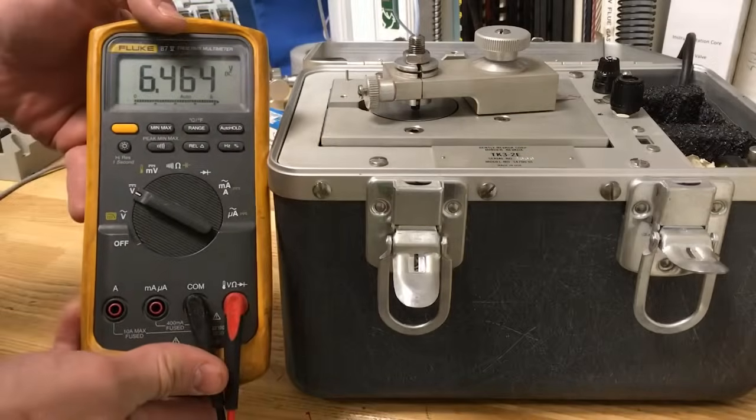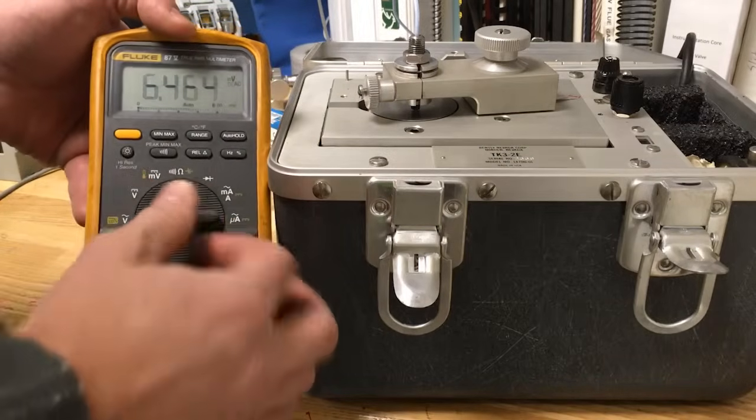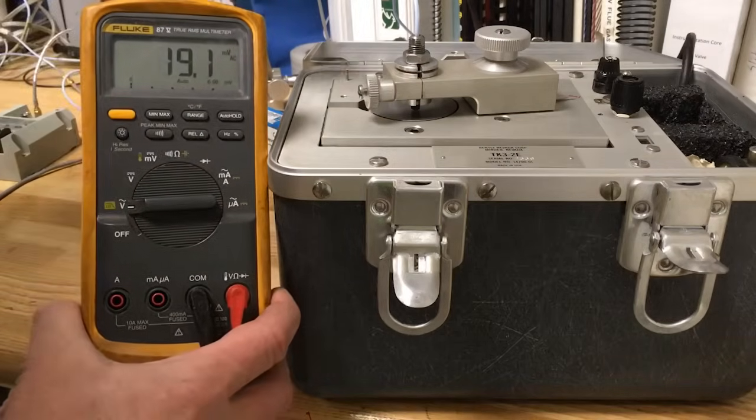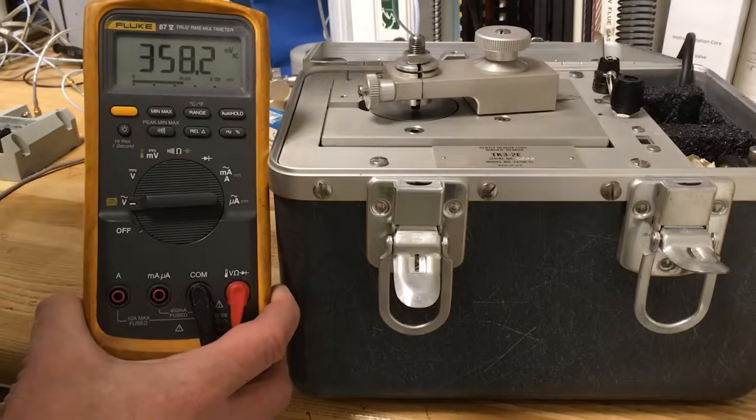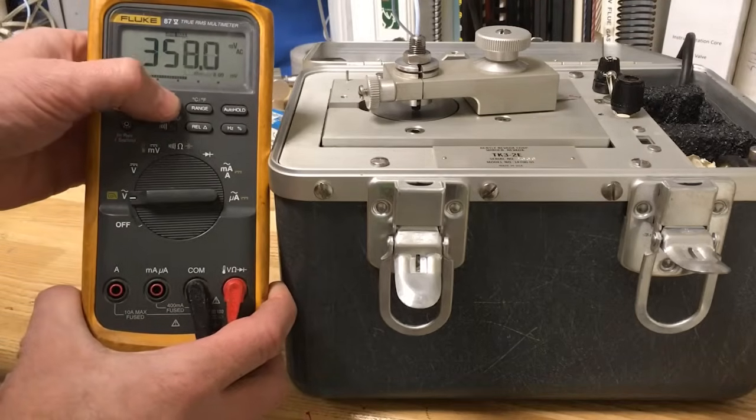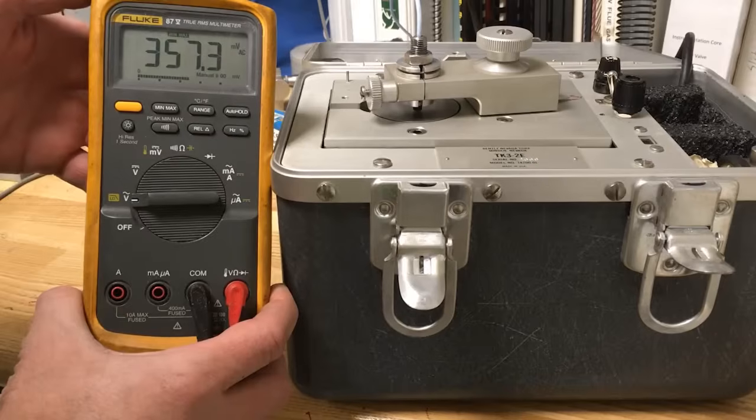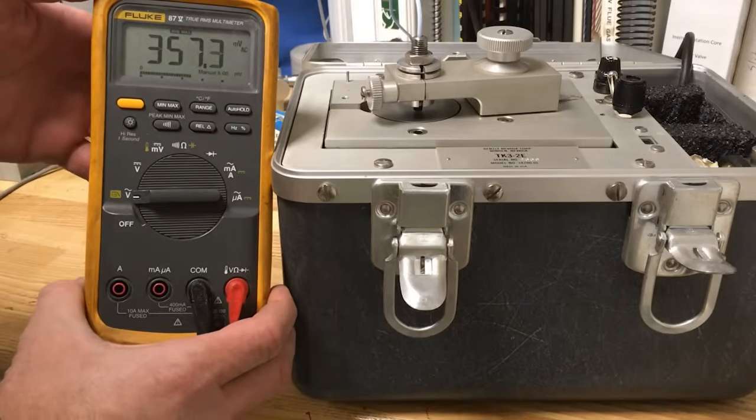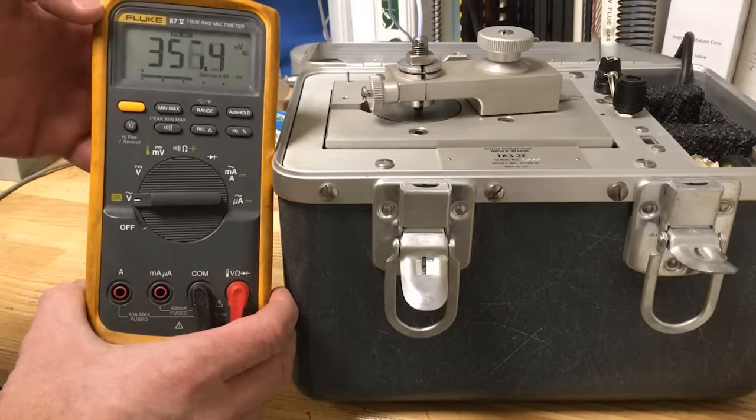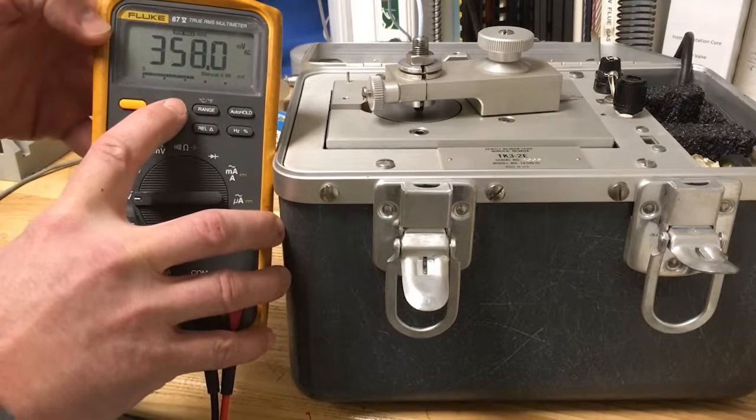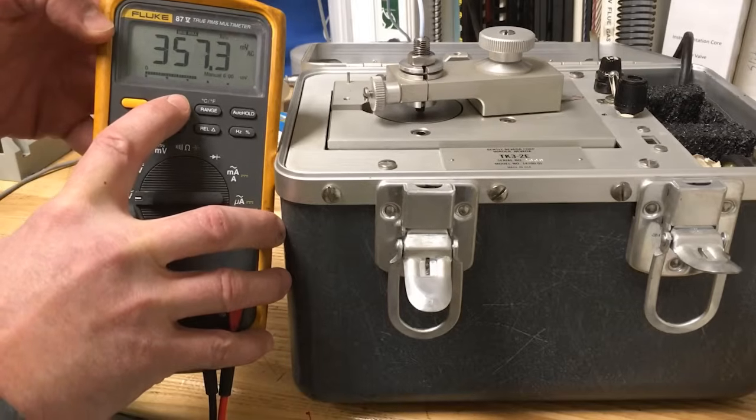Switch the voltmeter to read AC volts. Switch on the power and adjust the speed to the approximate speed of the machine the equipment will be installed on. If your multimeter is equipped with a min-max feature, this works the best. Just make sure that you do not activate this mode until the disc is rotating and the voltage value is stabilized.